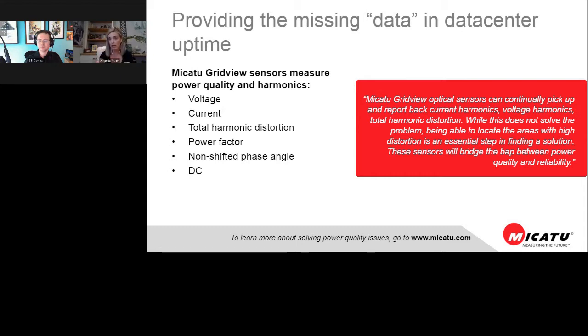So for all my electricity nerds out there, if you have a current transformer, a CT, one of the most dangerous things for somebody who works at the utility is an open CT circuit, because if you hit that, you're getting zapped, and zapped hard. We completely eliminate that risk. If there are transients that come across the grid, some anomaly in the power that's going to cause a big problem, if you have a measuring device that is an actual electrical circuit, it's going to feel that problem, and that could cause a catastrophic failure.